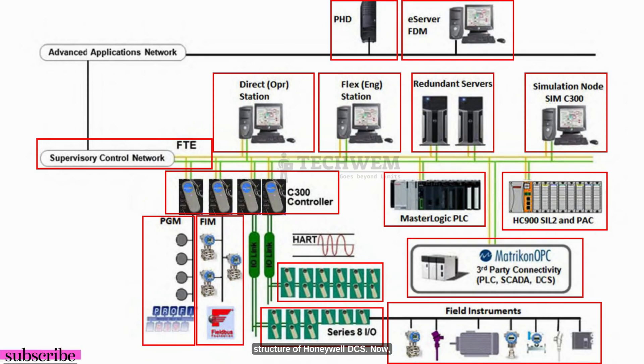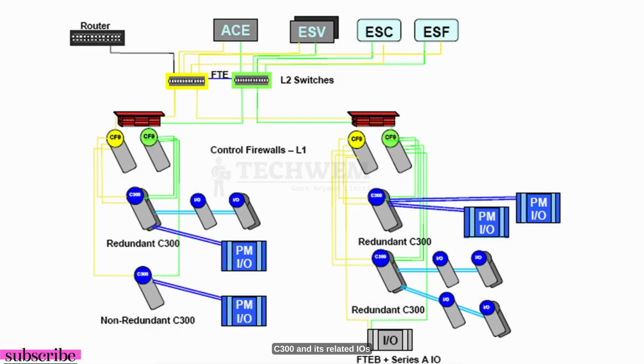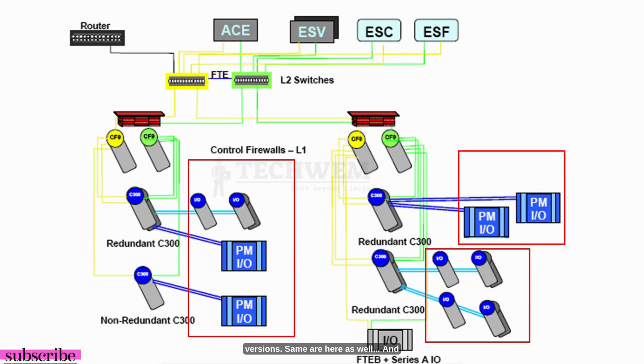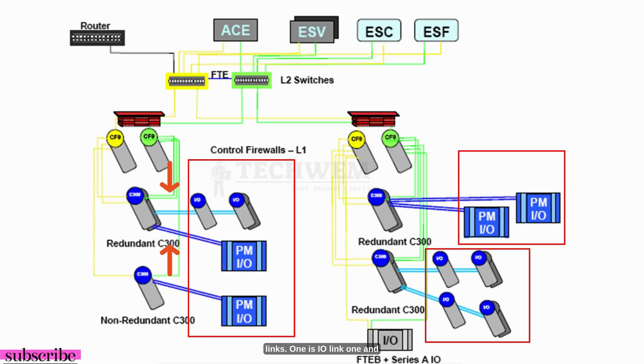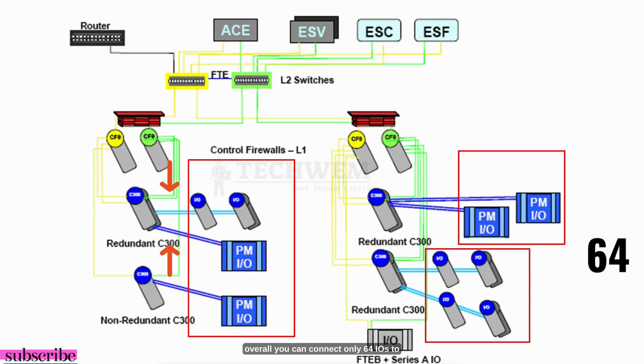This is the basic structure of Honeywell DCS. Now we are going to discuss this part in our next slide — a more elaborated slide for C300 and its related I/Os. Here you can see Series C I/Os and PM I/Os, the older versions. There are two I/O links: I/O link 1 and I/O link 2, on which you can connect different I/Os to a C300 controller. In terms of capacity, you can connect a maximum of 40 I/Os on each link, and overall a maximum of 64 I/Os to the C300.